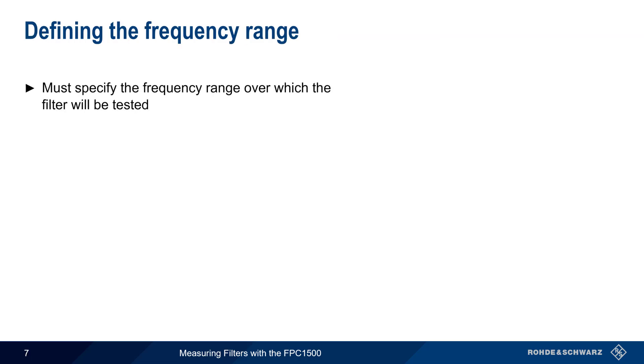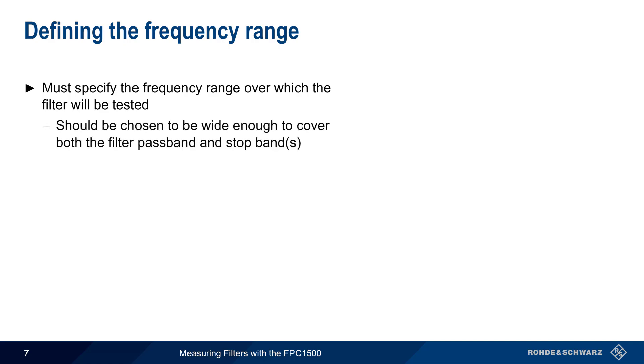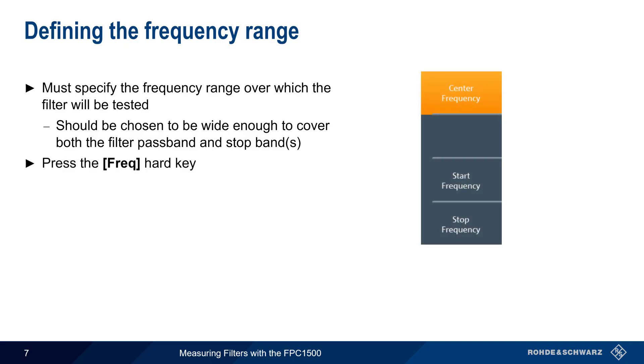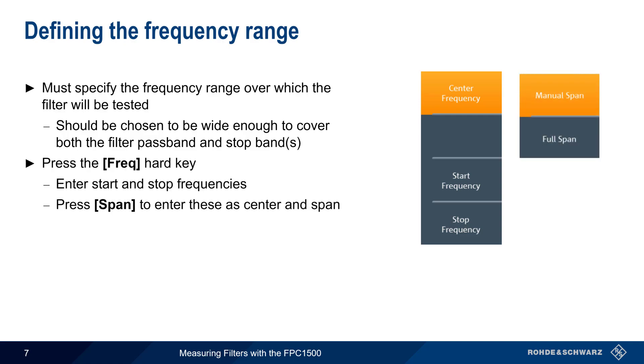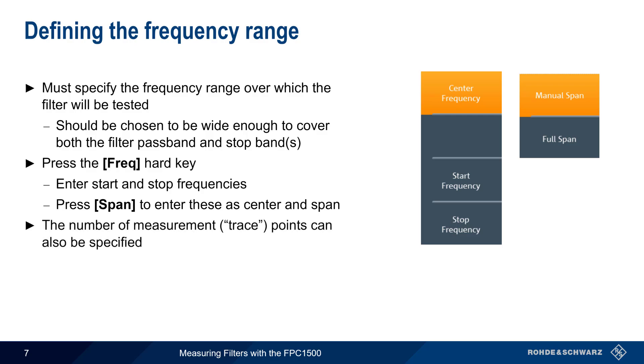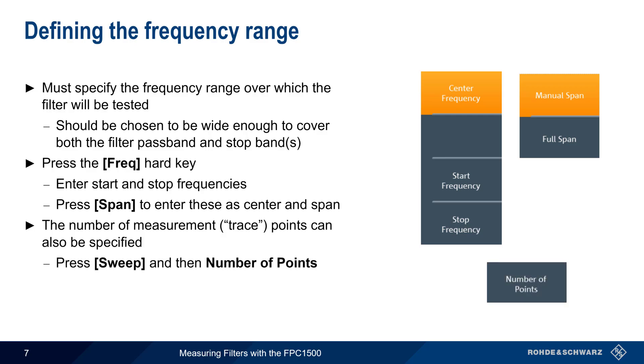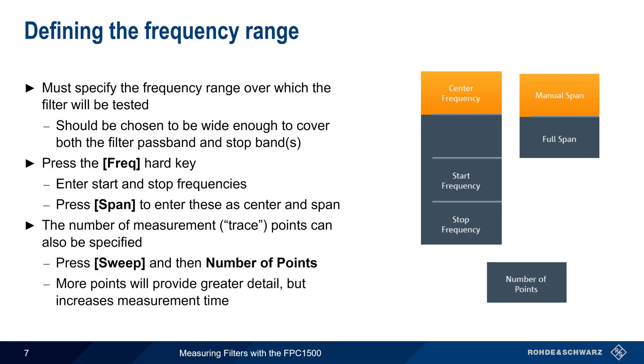We also need to specify the frequency range over which the filter will be tested. This should be wide enough to include both the filter pass band and some portion of the stop band. To define the frequency range, press the Frequency hard key and enter the start and stop frequencies. The Span key can also be used to enter these as center and span instead. The number of measurement or trace points over the span can also be specified by pressing the Sweep hard key and adjusting the number of points. A greater number of points will provide greater detail, but increases measurement time.